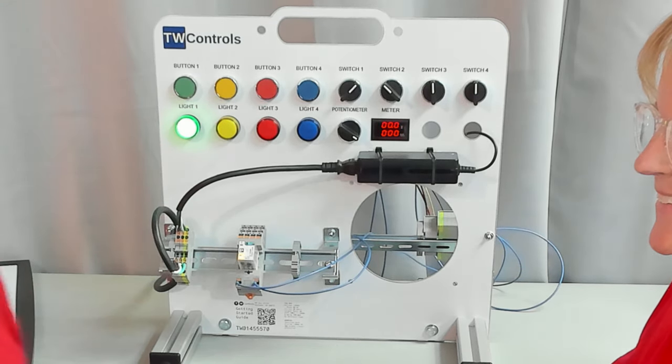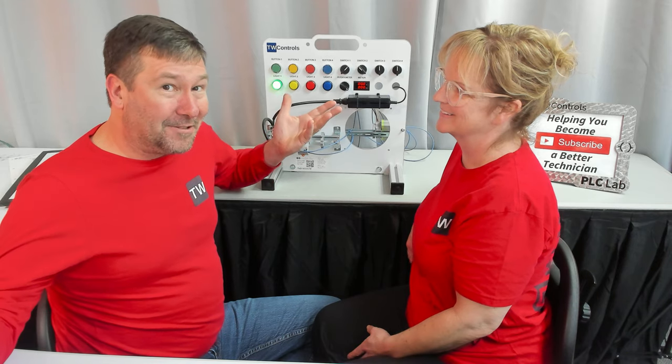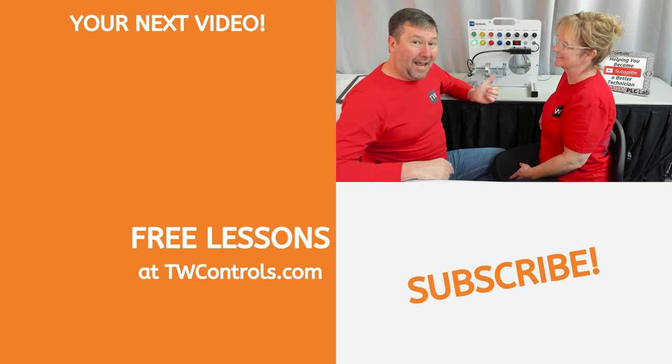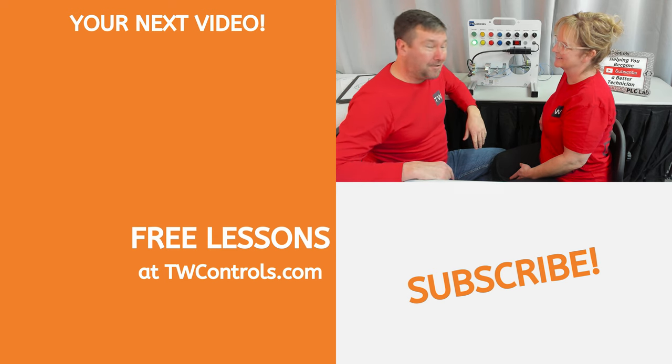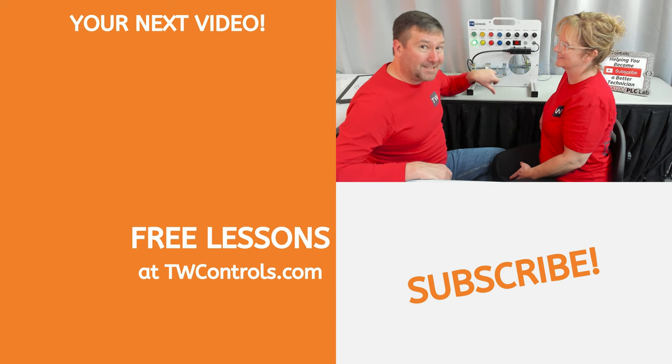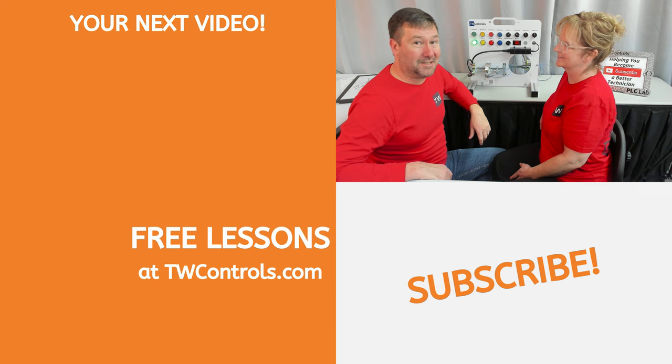So accidentally, there's a real good example of what can happen if you connect the wires wrong on what they call a polarized relay, or relay that specs out which one is the plus and which one is the minus.